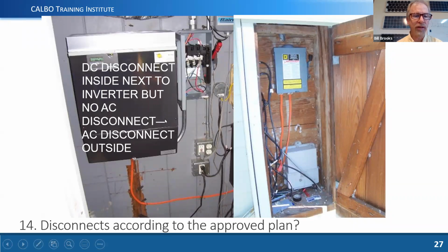Here's an example where the DC disconnect is next to the inverter, as it should be, but the AC comes out, and then this is inside of like a utility room, and then this particular enclosure is on the outside of the house, and the wire punches through the wall and comes into this AC disconnect. Unfortunately, this is on the outside of the house, and this is on the inside of the house, so there's no way to visibly see this disconnect from the inverter.